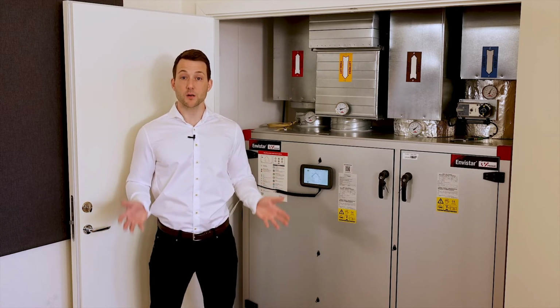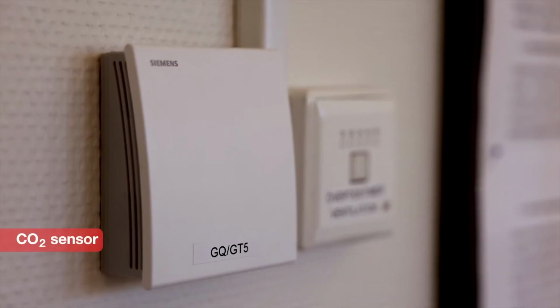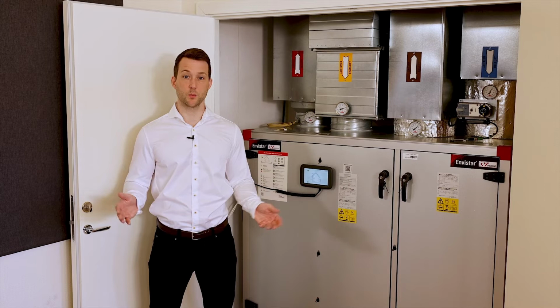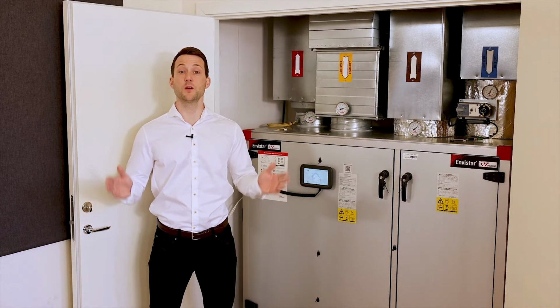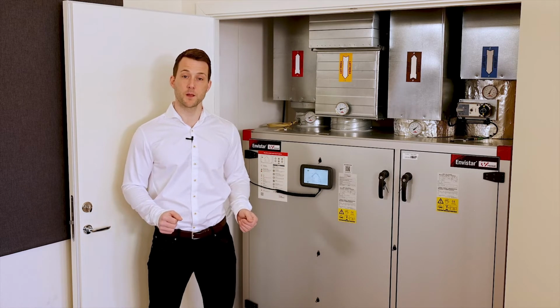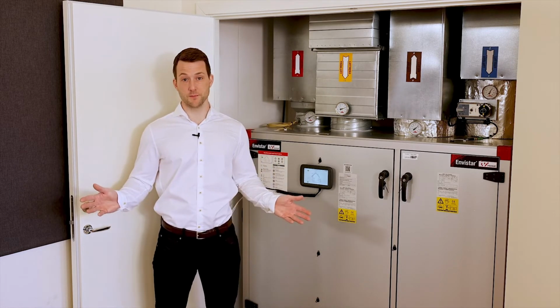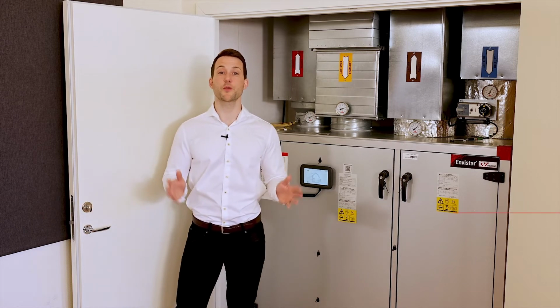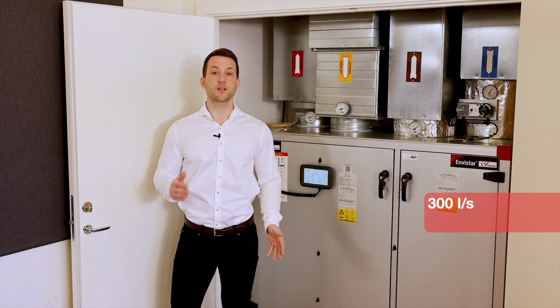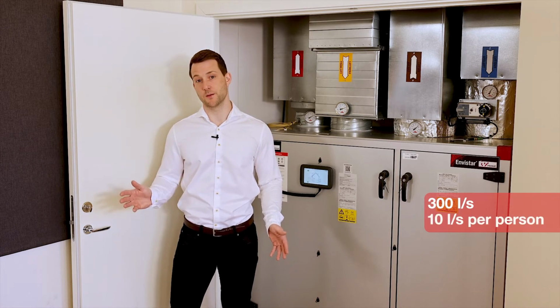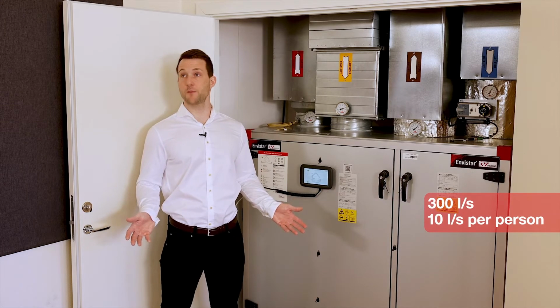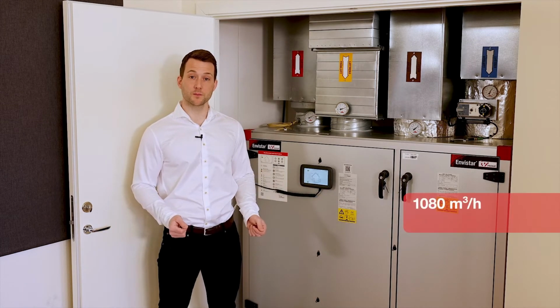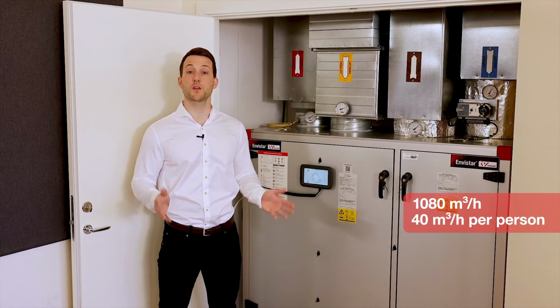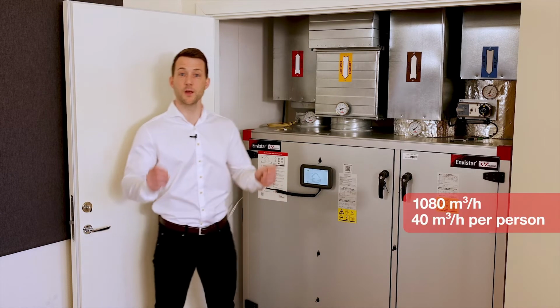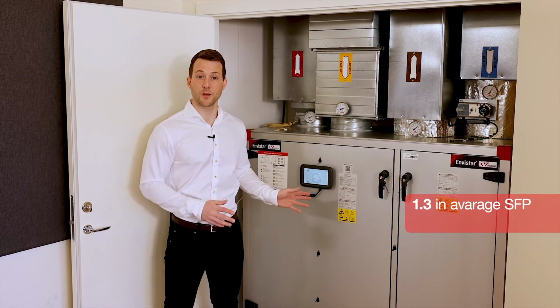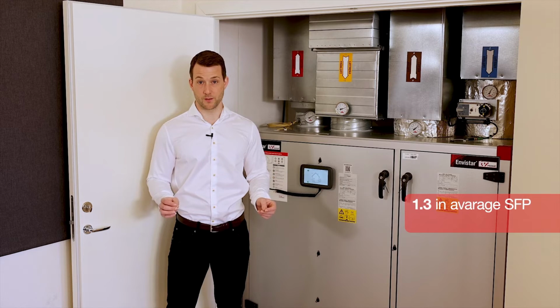And after that, depending on the amount of persons in this classroom, a CO2 sensor is regulating the airflow, which means whenever the CO2 level reaches above 800 ppm, the airflow increases steplessly up to a set point of around 300 liters per second. That is above 10 liters per second and person. In cubic meters per hour, you would say 1080 cubic meters per hour, which equals around 40 cubic meters per hour per person. The average annual SFP value on this unit is only 1.3.